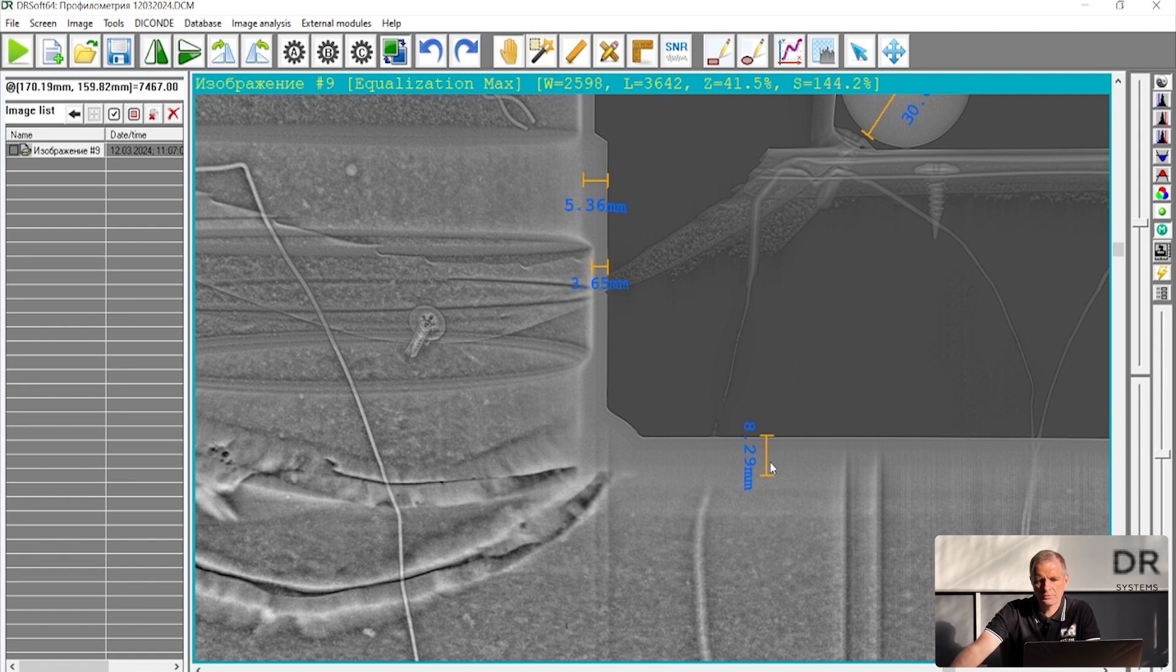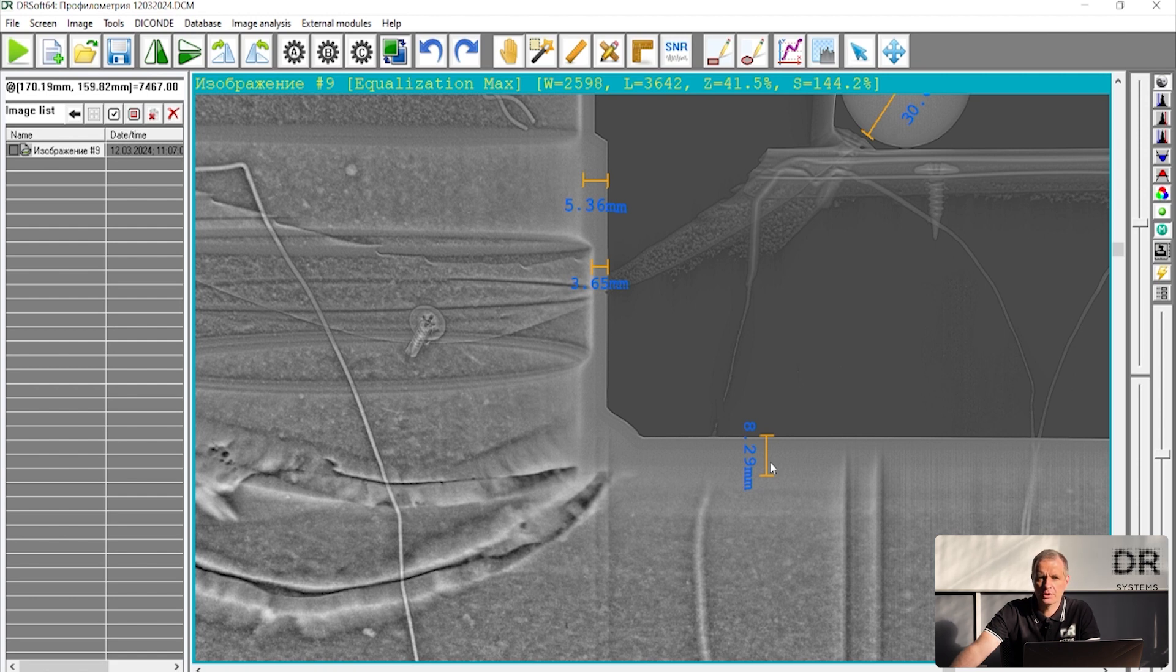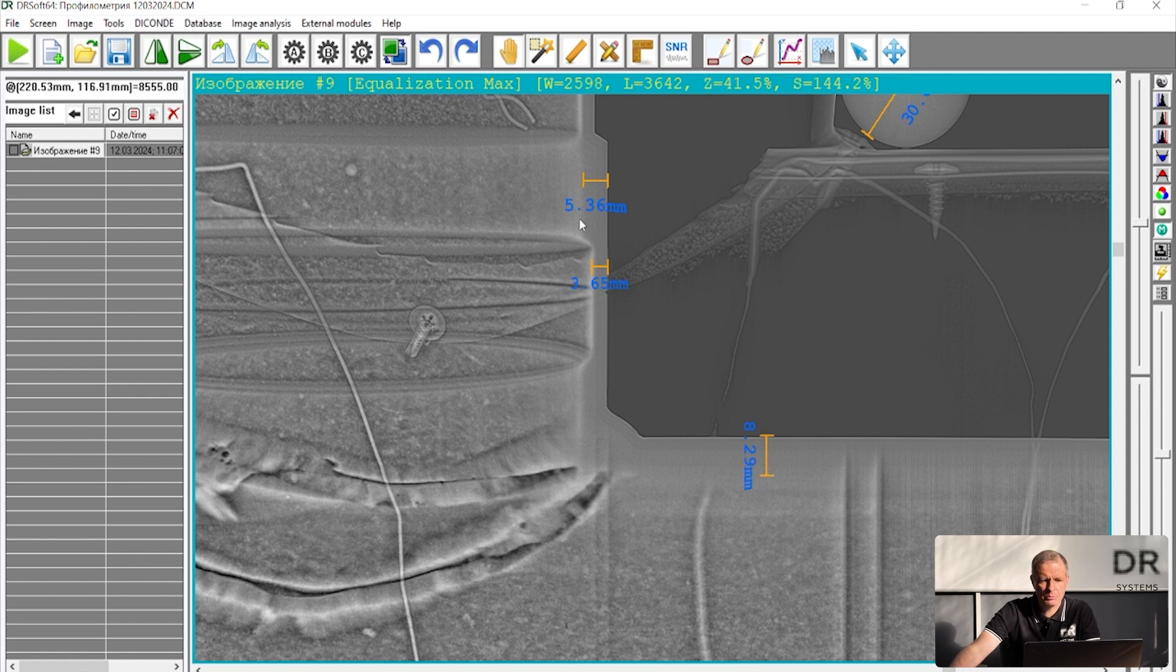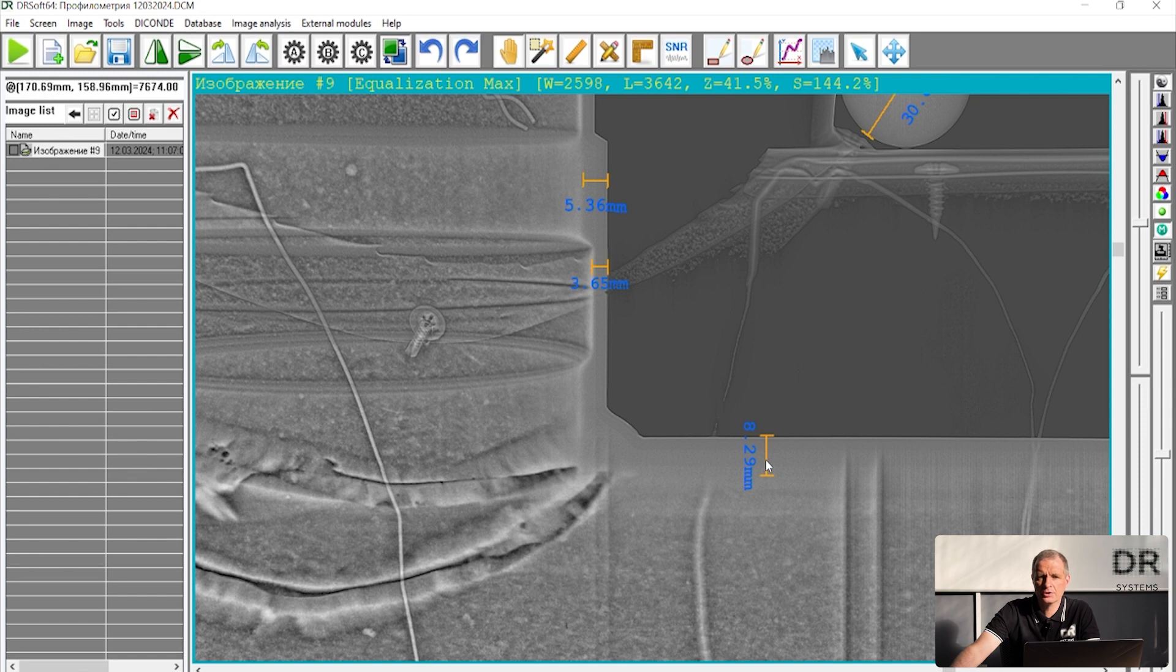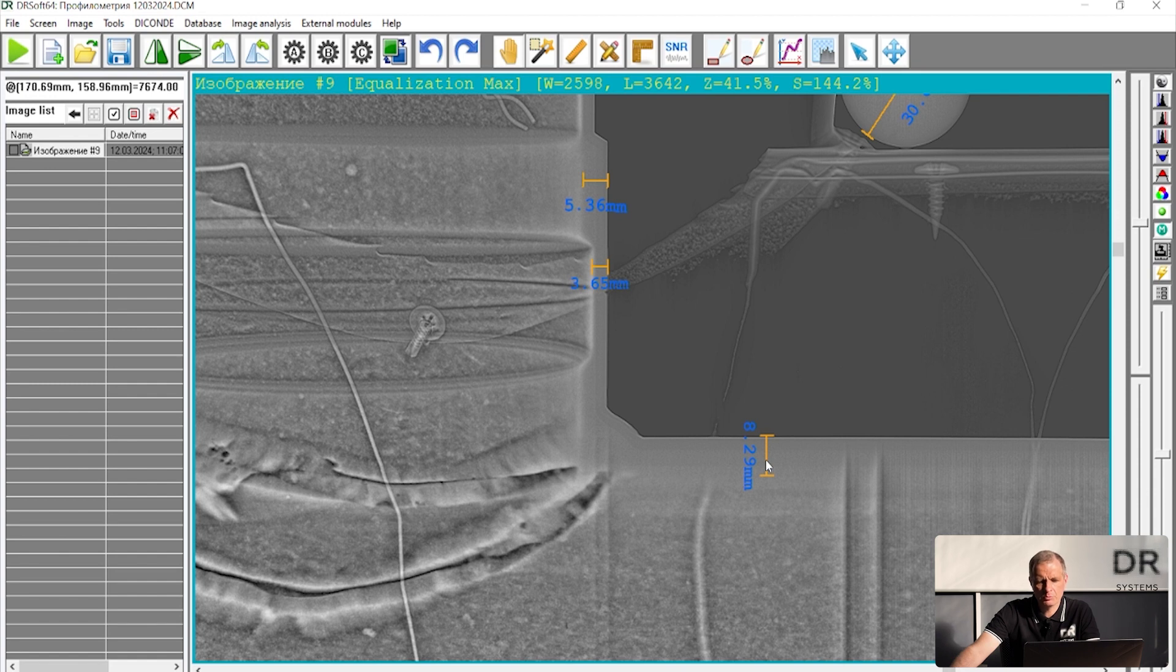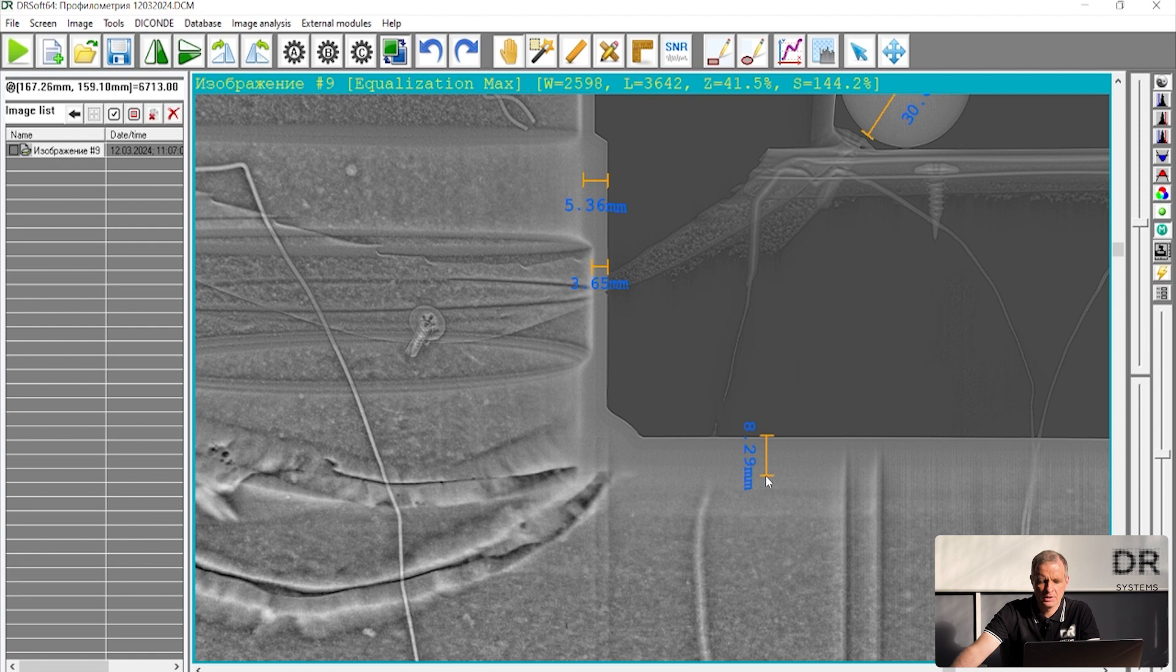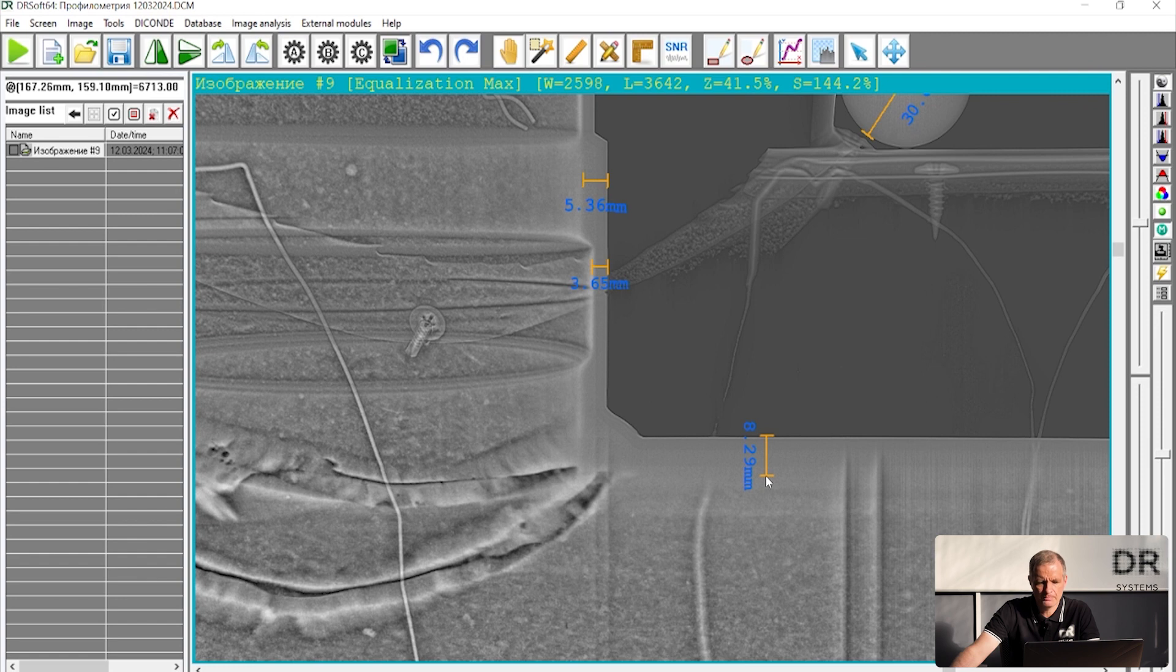And if you want to measure the wall thickness here, you need a stronger x-ray or gamma source. In this case, for example, we used 300 kV and the pipe is 6 inch, which is too big for this x-ray source. And what we need is to use Iridium 192, and the image will be brighter and you will see the inside of the wall. So here it's not possible to measure just because you cannot see the inside of the pipe.